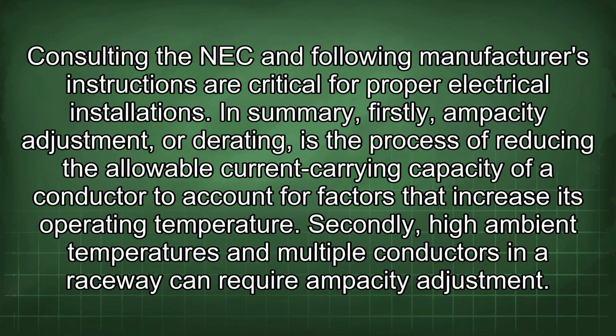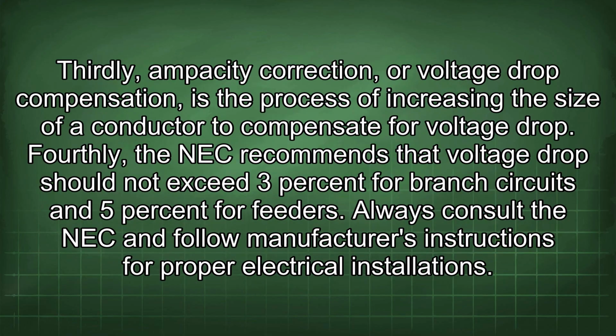In summary, firstly, ampacity adjustment, or derating, is the process of reducing the allowable current carrying capacity of a conductor to account for factors that increase its operating temperature. Secondly, high ambient temperatures and multiple conductors in a raceway can require ampacity adjustment. Thirdly, ampacity correction, or voltage drop compensation, is the process of increasing the size of a conductor to compensate for voltage drop. Fourthly, the NEC recommends that voltage drop should not exceed 3% for branch circuits and 5% for feeders. Always consult the NEC and follow manufacturer's instructions for proper electrical installations.